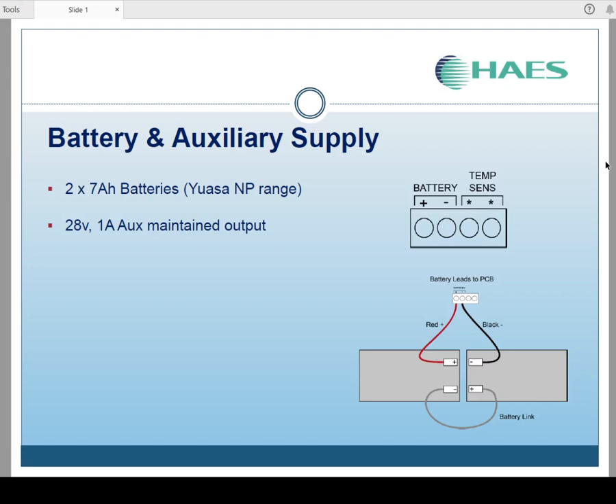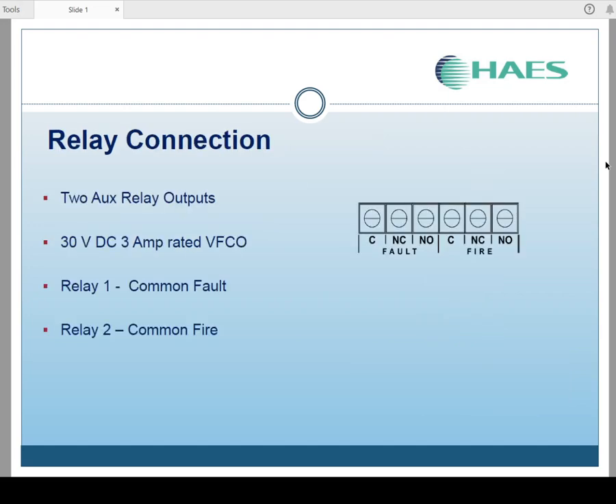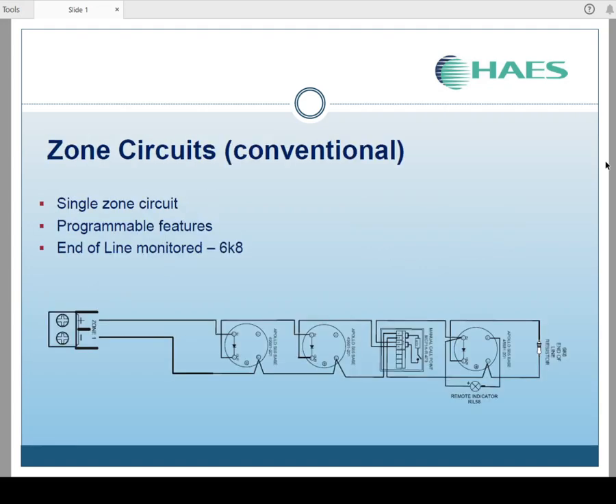We recommend the Yuasa range. And there's also the 28 volt 1 amp maintained output there suitable for magnetic control. Batteries should be wired in series as per any other panel with 28 volts. The panel comes with the two relays inside, both rated at 30 volts DC at 3 amps. They're voltage free changeover contacts, one fire and one fault relay. The zone circuit or detector circuit can be wired conventionally. It gives you a single zone of detectors.